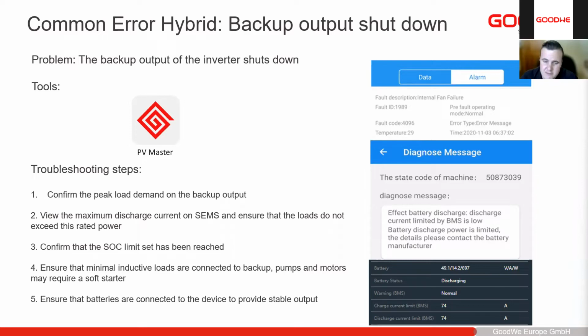Very often we have to check what type of loads are running on the backup output. So inductive loads are unfortunately a problem, especially when there are cheaper inductive loads. Very cheap motors and pumps and things like that often have horrible power factors and just consume way too much power when they start up. That might require a soft starter to help mitigate the inrush currents, especially if you do require to use it under backup.